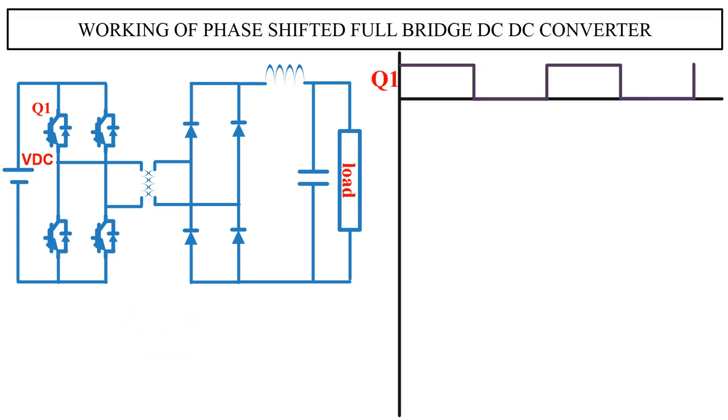This is the PWM for switch Q1. To avoid shoot through, the PWM signal for Q2 should be 180 degrees out of phase with respect to Q1. So this is the PWM for switch Q2.